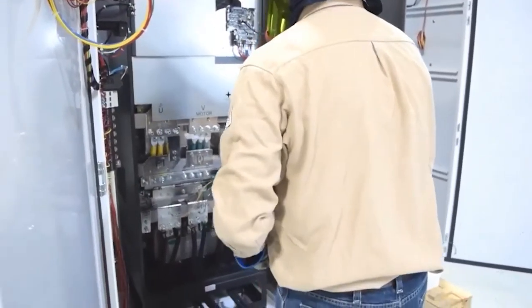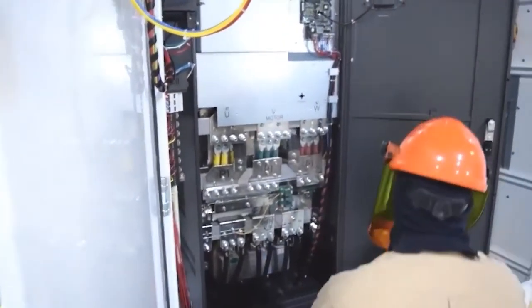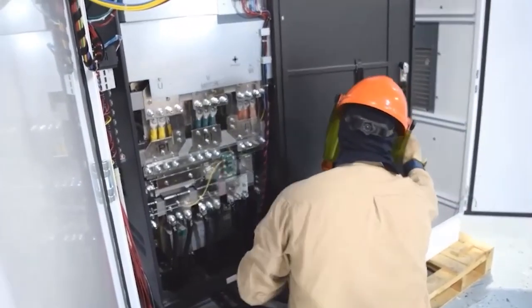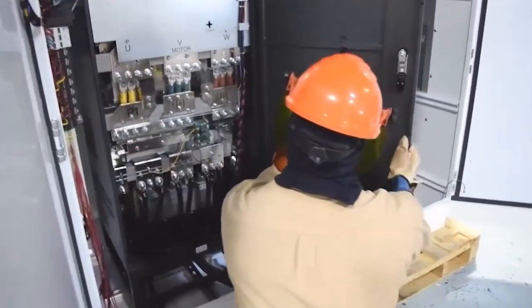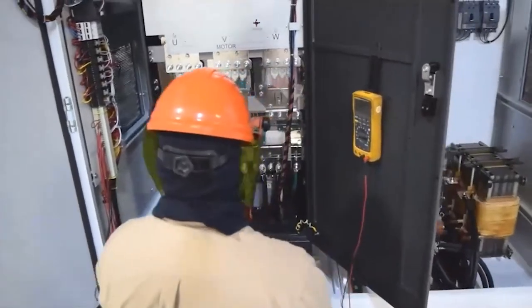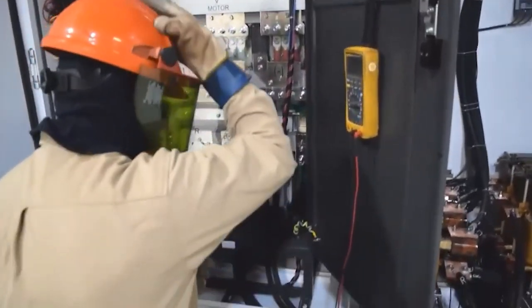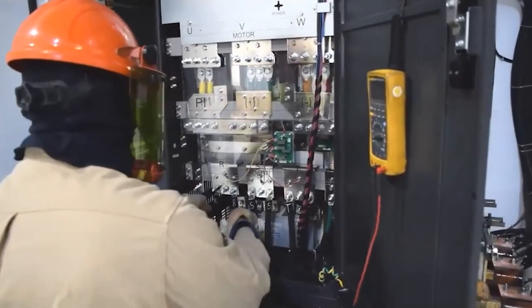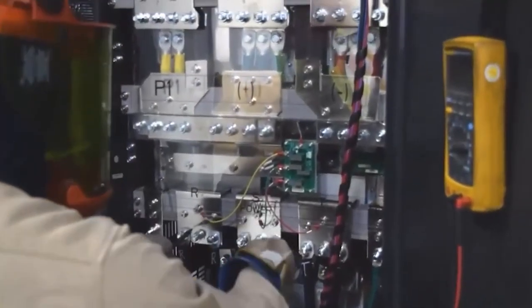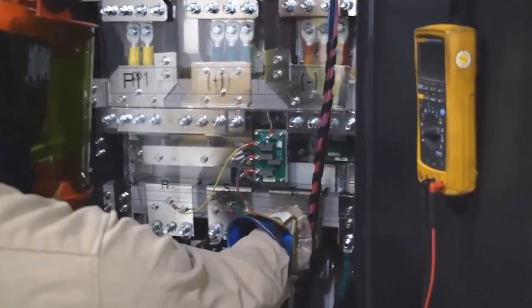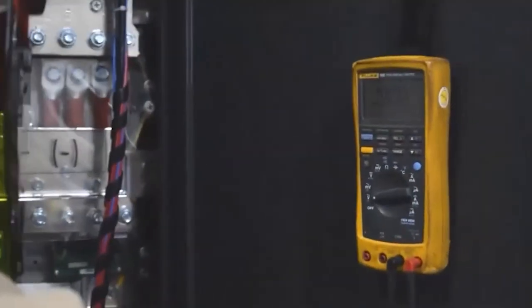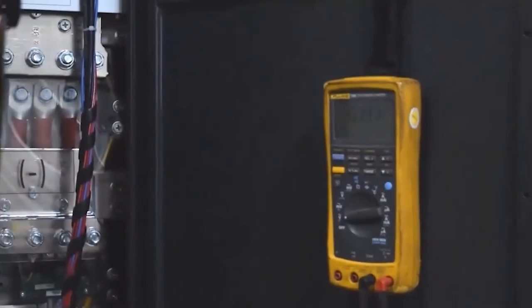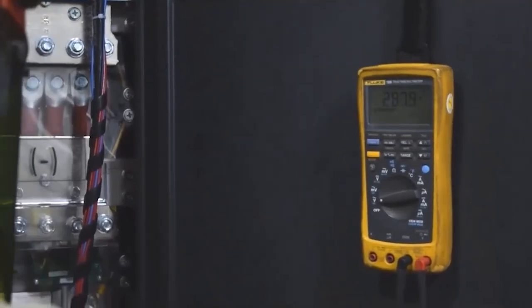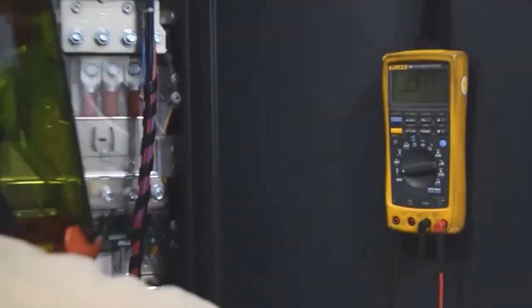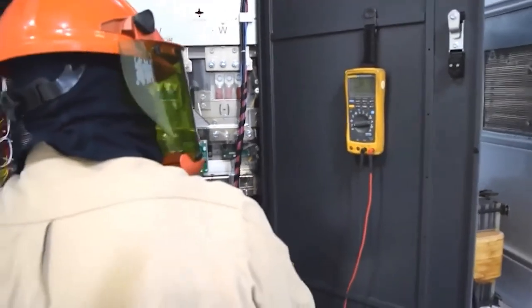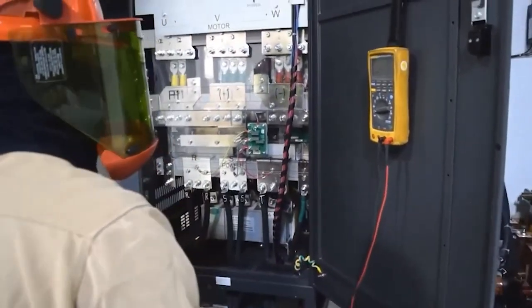Okay, I'm going to get inside the cabinet now. And I'm going to measure all my incoming voltages into the VFD again. And then once again, it's always phase to phase and phase to ground. Make sure I don't have anything that I'm losing there. Voltages coming into the VFD should be basically what your line voltages are coming into the cabinet. If you have a harmonic filter, they may be just a little different, but they should be pretty close.